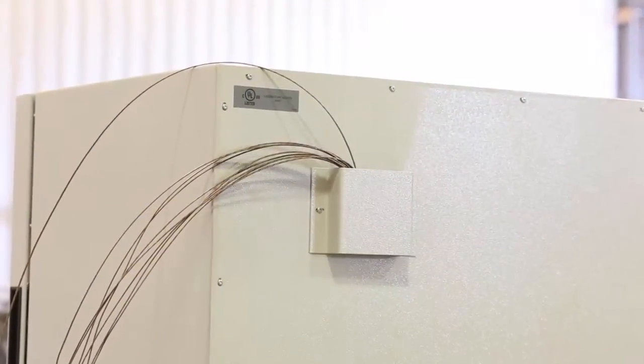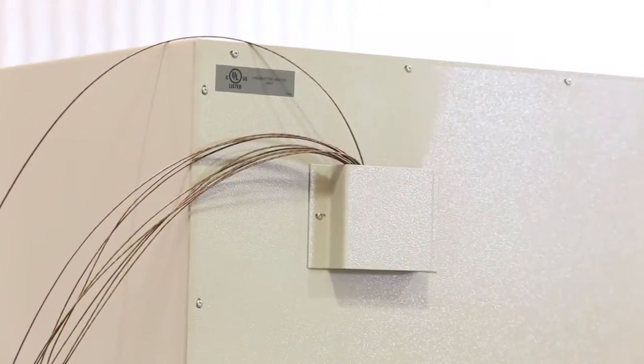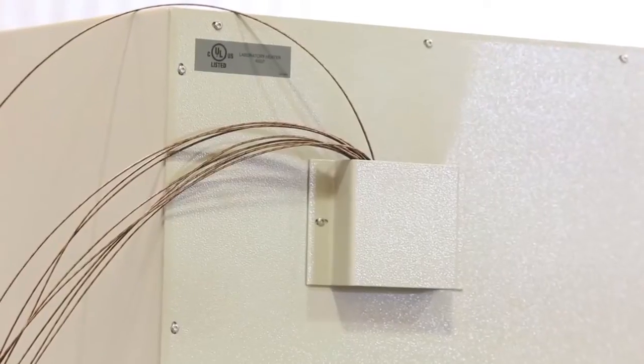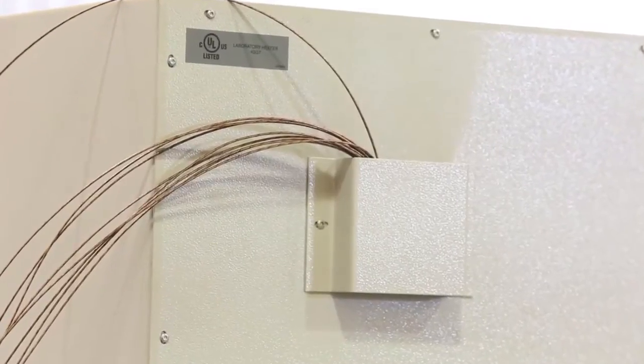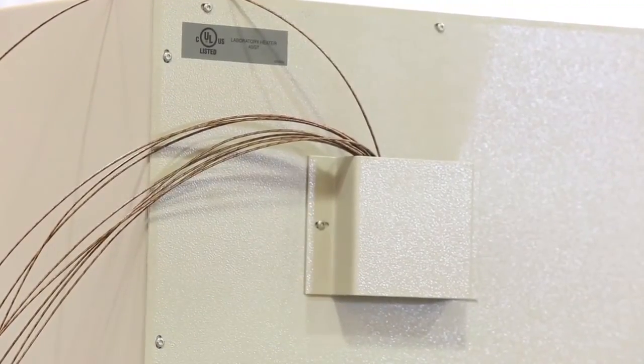At high temperatures, take care that the point where the thermocouple wires enter the oven remains constant. Changing this hot-cold transition point can cause shifts in the calibration.